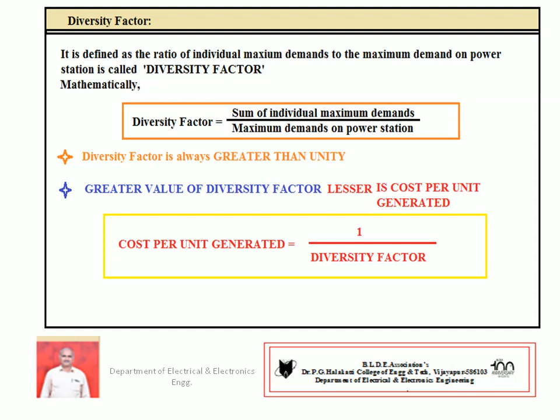Already we have seen many factors. One more factor is the diversity factor. The diversity factor is defined as the ratio of the sum of individual maximum demands to the maximum demand on the power station. Hence, the sum of individual maximum demands is always greater, so naturally the diversity factor is greater than 1. It is inversely proportional to the cost of generated power. Hence, as per good design and cost consideration, the diversity factor should be high. Remember that the diversity factor should be high.